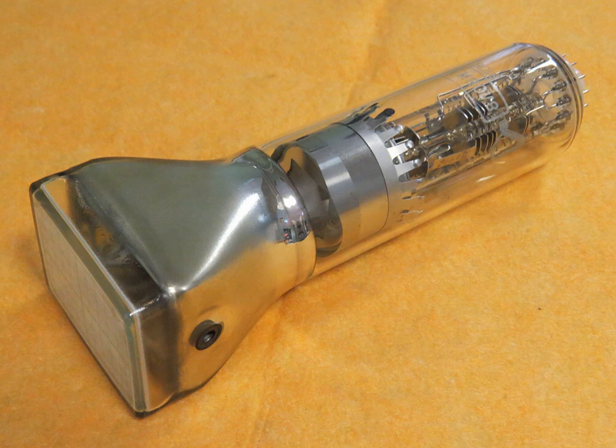Either a spring return switch position or a pushbutton arms single sweeps. A trigger level control varies the voltage required to generate a trigger, and the slope switch selects positive going or negative going polarity at the selected trigger level.